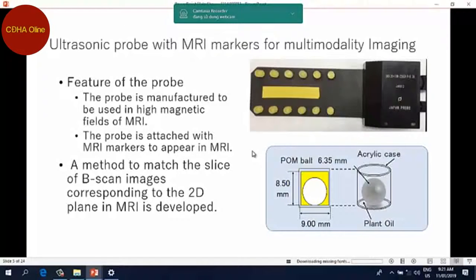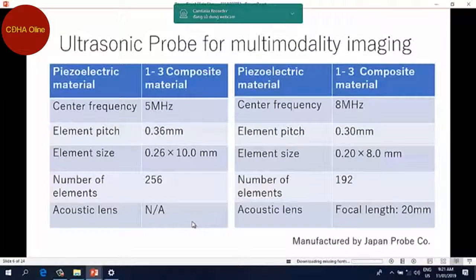We developed two types of probe. This is the low frequency, 5 MHz, and this is the 8 MHz. The frequency is different, and also the element pitch is different. This is 0.36, and this is 0.30. The number of elements is 256, and this is 192. I'd also like to add a comment on the acoustic lens. It's not available, but this is a focal length of 20 millimeters. This is the first developed type of probe, and the second developed probe is here. These two probes are used in high magnetic fields.